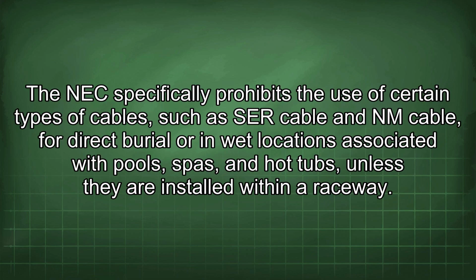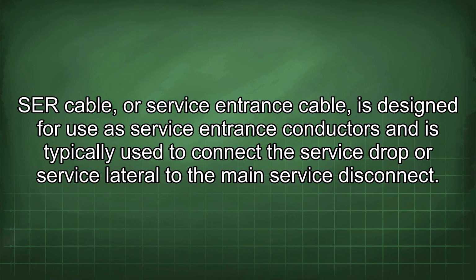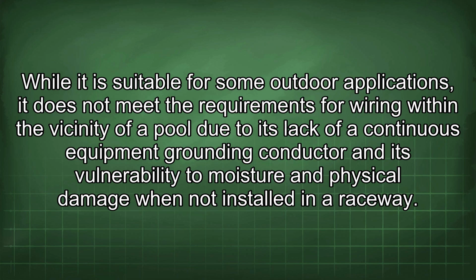The NEC specifically prohibits the use of certain types of cables, such as SER cable and NM cable, for direct burial or in wet locations associated with pools, spas, and hot tubs, unless they are installed within a raceway. SER cable, or service entrance cable, is designed for use as service entrance conductors and is typically used to connect the service drop or service lateral to the main service disconnect. While it is suitable for some outdoor applications, it does not meet the requirements for wiring within the vicinity of a pool due to its lack of a continuous equipment grounding conductor and its vulnerability to moisture and physical damage when not installed in a raceway.